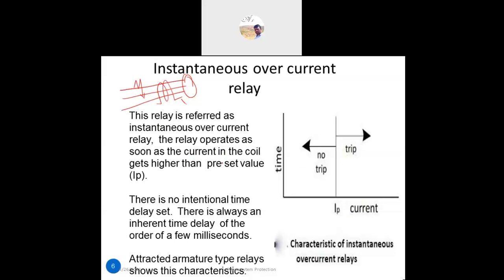There is always an inherent time delay of the order of milliseconds for the instantaneous relay, but no intentional delay is set. When the fault occurs and the current goes beyond the pickup value, it will trip immediately. The attracted armature type relay shows these characteristics — it is the electromagnetic relay type that exhibits instantaneous operation.